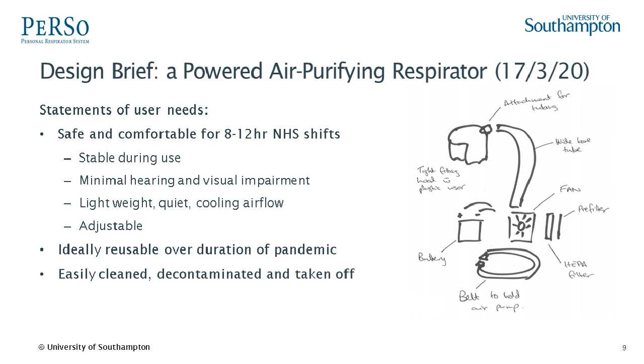So, as the previous speakers mentioned, somehow on a very short timescale, within 72 hours, we produced the first prototype. This uses a HEPA filter, much like that found in your vacuum cleaner or dehumidifier, which should in theory capture both the most common fomite or droplet sizes, which are produced during talking, coughing or sneezing, as well as much smaller individual virions or virus particles. And I can discuss the mechanics of that for anybody who's particularly interested later on. It's important to note that not all HEPA filters are equal. There is a standard again, so we tested 2 particular grades.